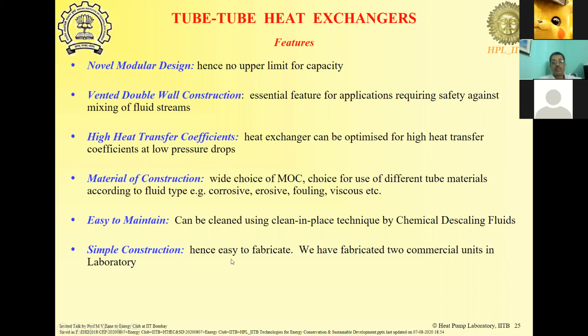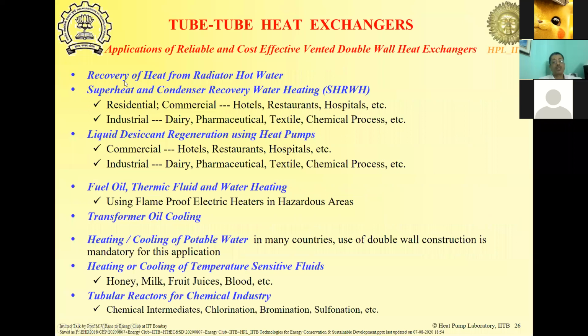Some of the applications that we have deployed it for are radiator hot water heat recovery, superheat condenser heat recovery, liquid desiccant based multi-utility heat pumps, fuel oil heating, thermic fluid heating, water heating, transformer oil cooling, heating and cooling of potable water, and also shear sensitive and temperature sensitive fluids can be heated. Temperature sensitive fluids like honey, and fruit juices with fibrous material can be heated or cooled in this unit. And tubular heat exchangers can also be used as reactors for various chemical engineering processes while recovering the heat.